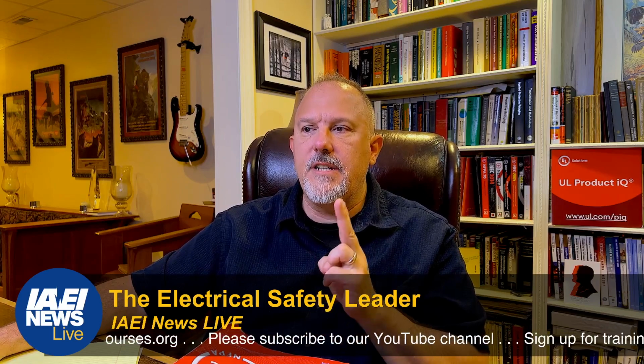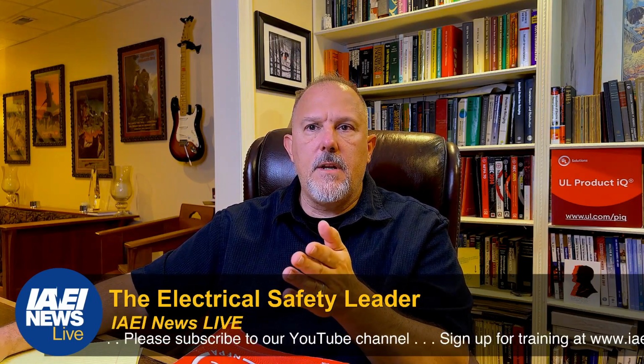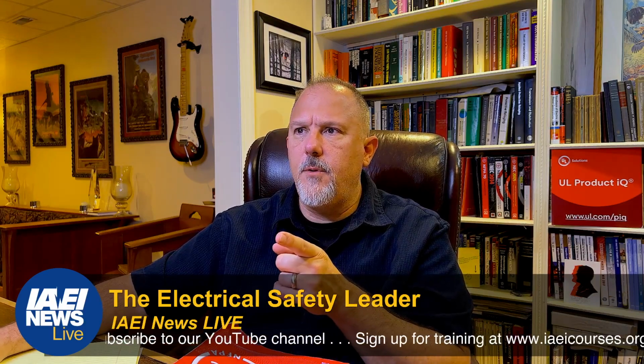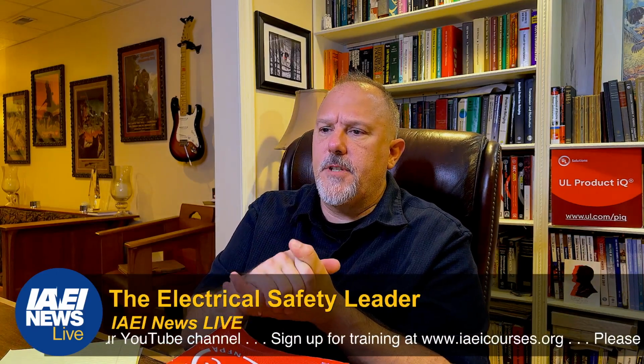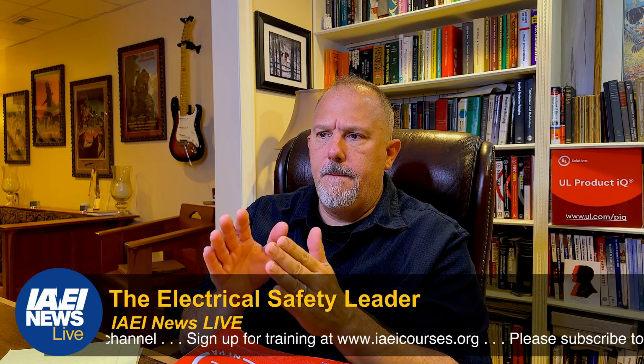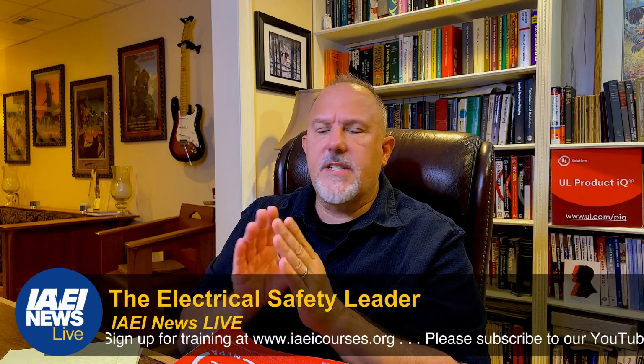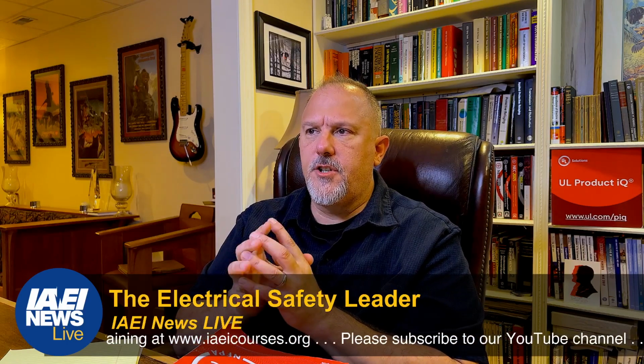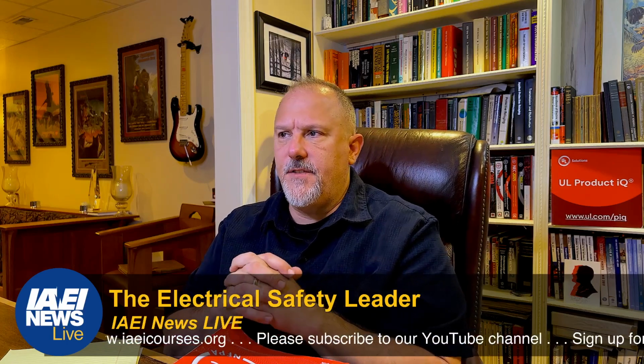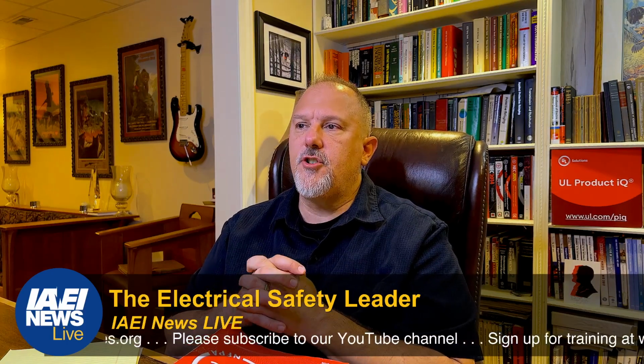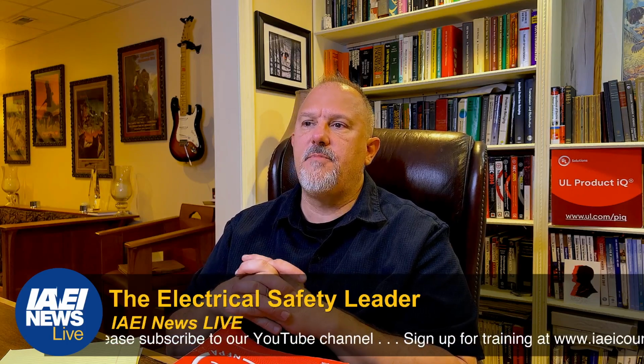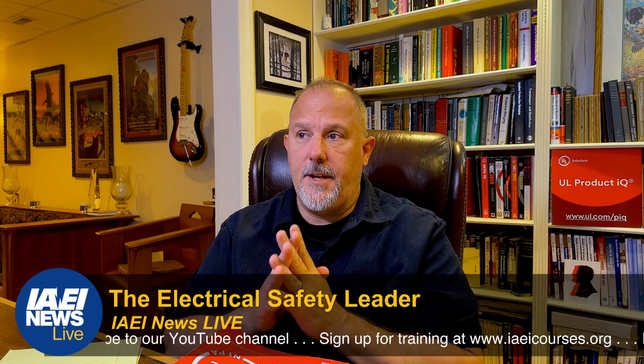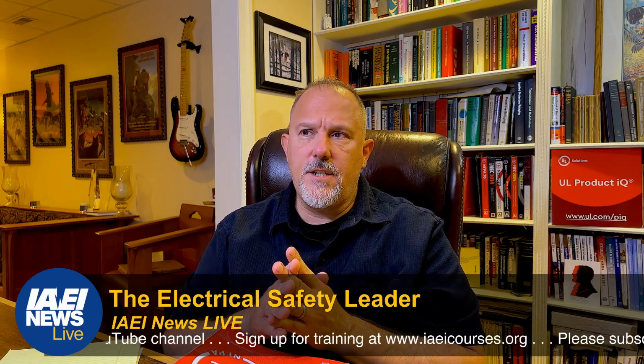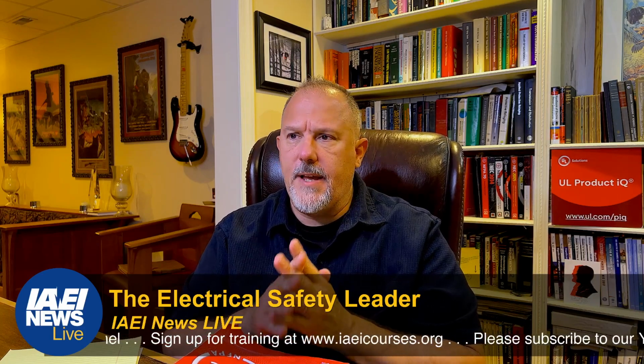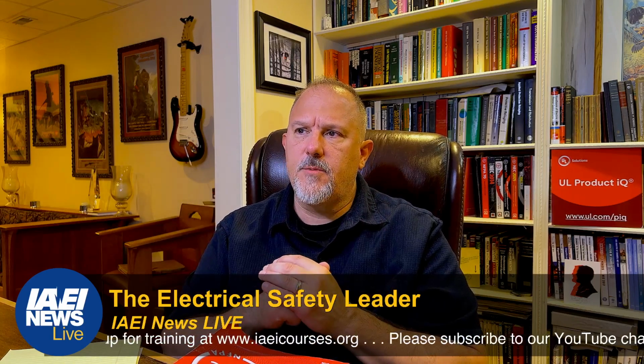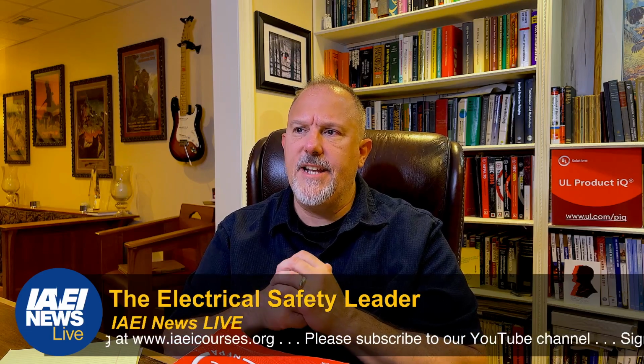230.94, relative location of overcurrent device and other service equipment. Did I get that right? 230.94. Yes. Relative location. So this is where the overcurrent device shall be protected. This tells us, in an exception, I believe it's Exception Number 2: high impedance shunt circuits, surge arresters, Type 1 surge protective devices, surge protective capacitors, and instrument transformers shall be permitted to be connected and installed on the supply side of the service disconnecting means as permitted by 230.82. So that's just telling you the relative location of the overcurrent protective device in regard to that other equipment, which in this case is the surge arresters, Type 1 surge protective devices, et cetera.